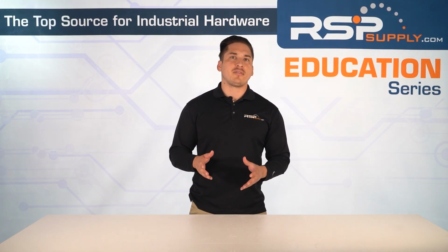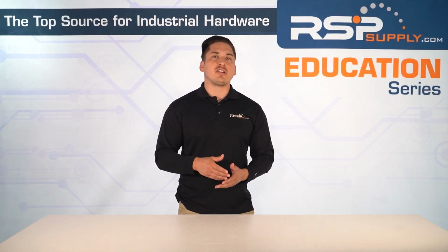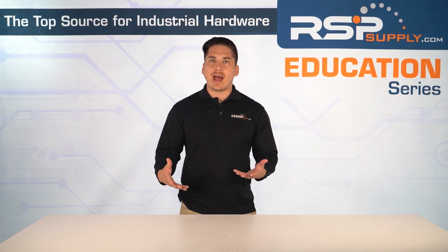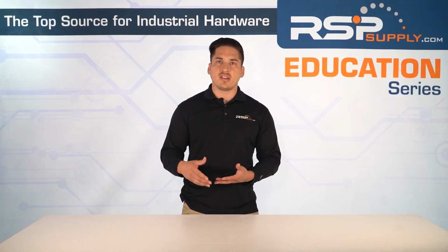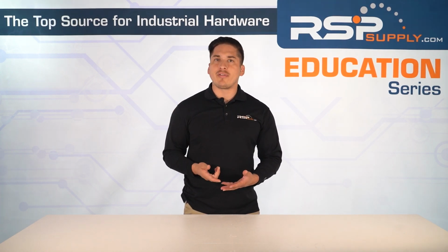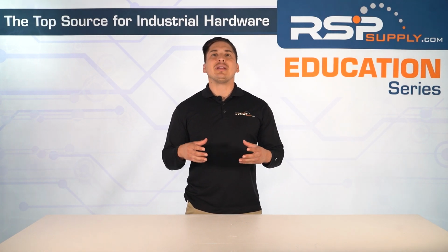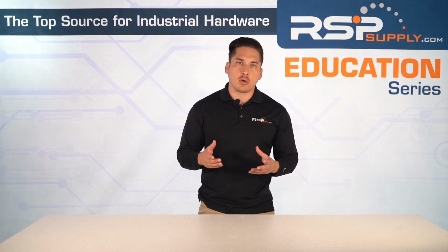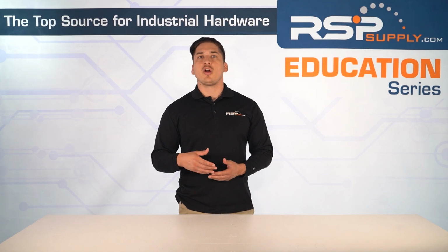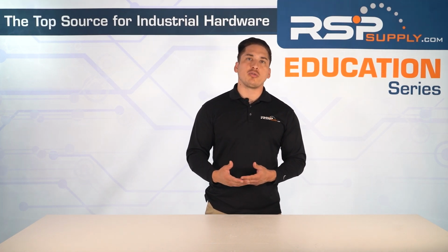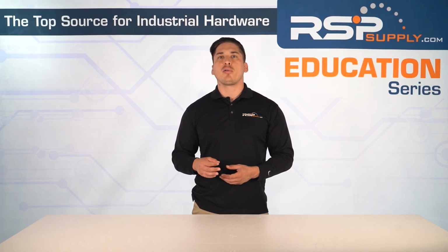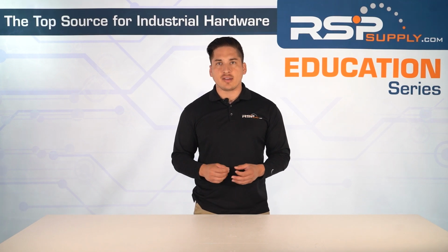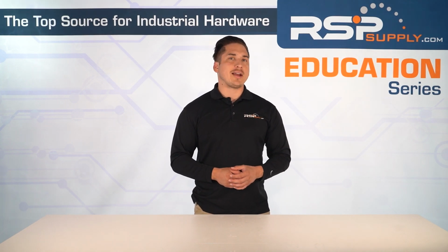Let's talk explosive environments. You're going to need to use rated switches only. So if the area has explosive gases or dust in the air, like in oil refineries or grain facilities, you need a disconnect that's approved for hazardous locations. Look for Class 1 or Class 2, Division 1 or Division 2 ratings per NEC and UL guidelines. These switches are built to handle those kinds of dangers.